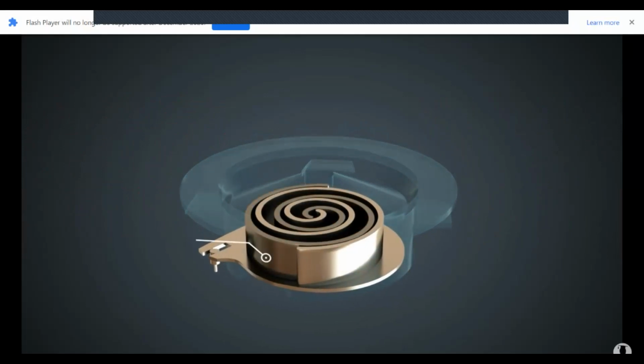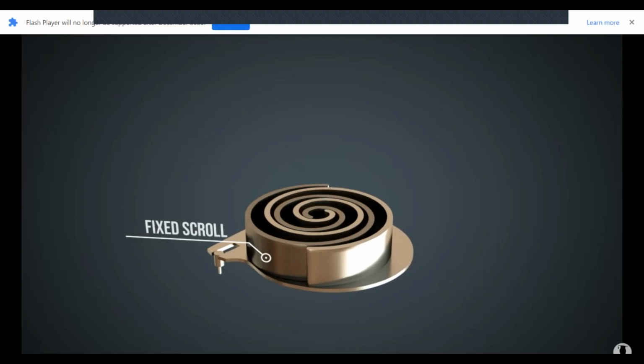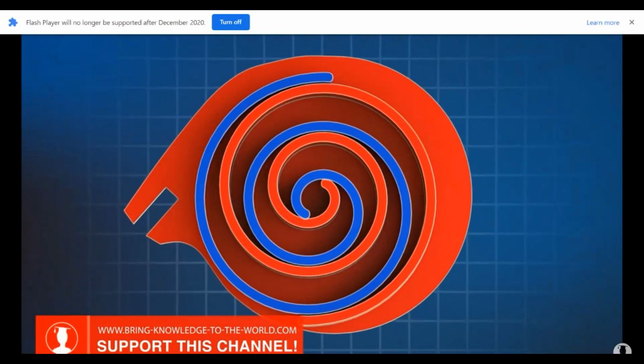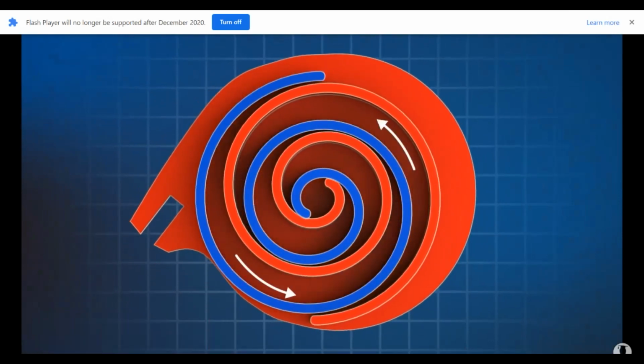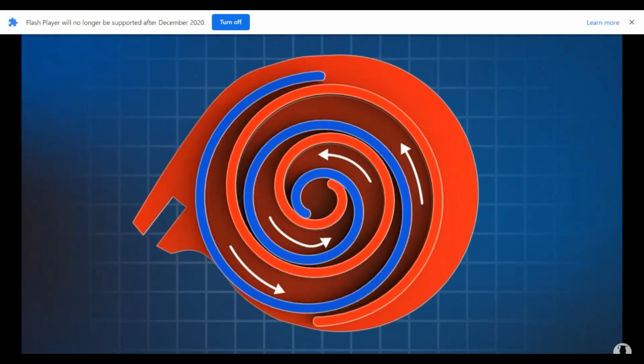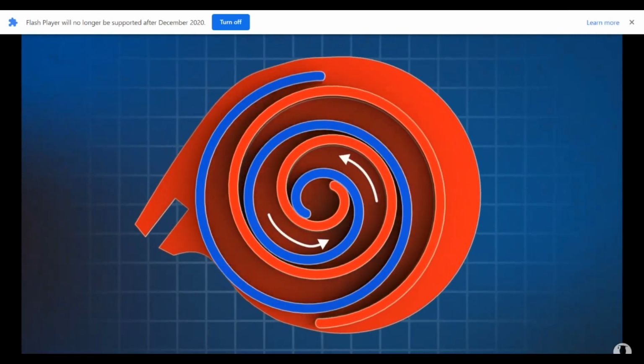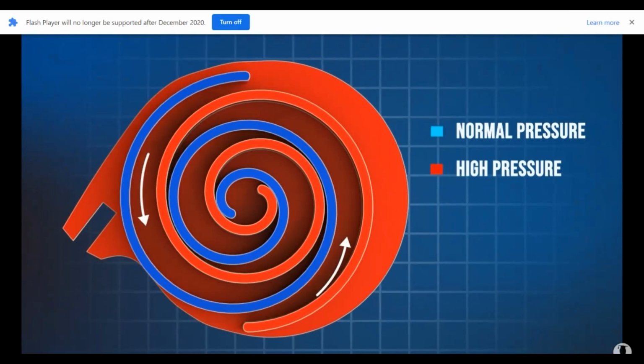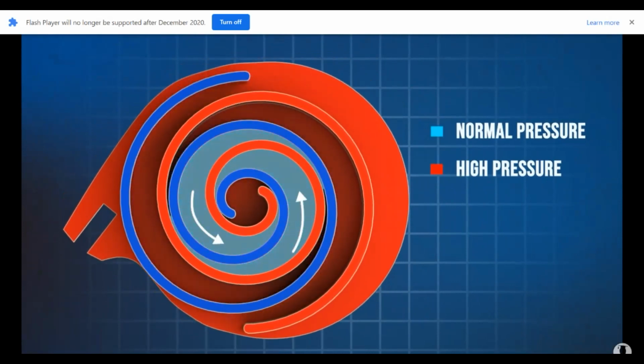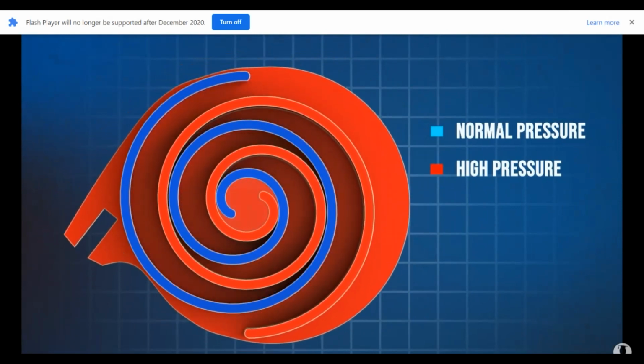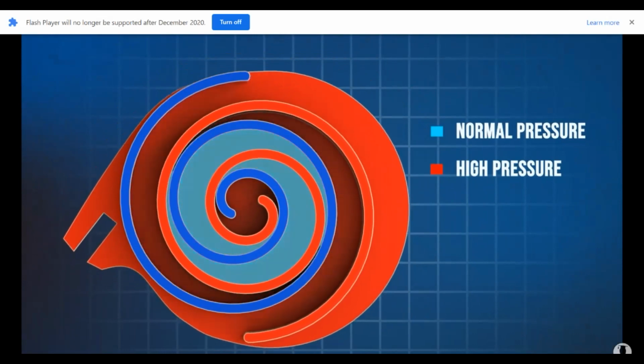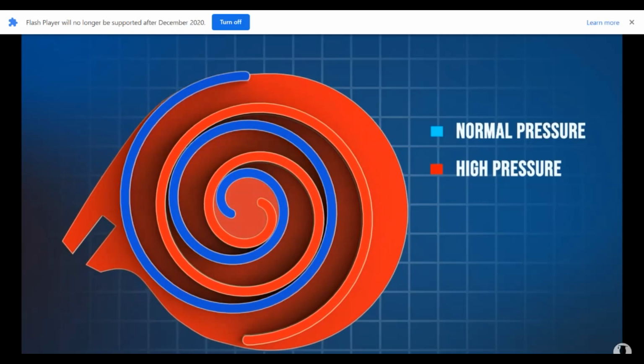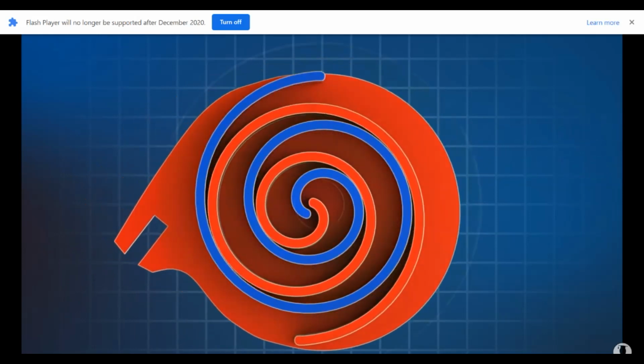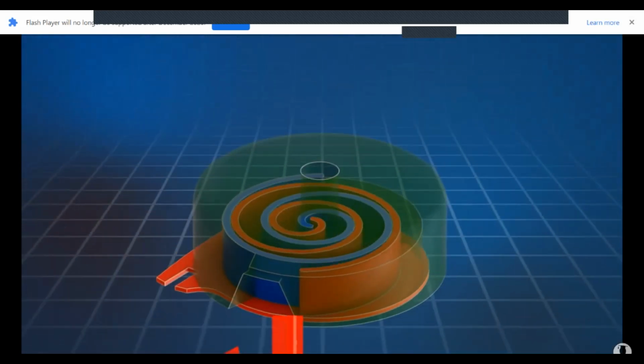For better visibility, only the moving scroll with its base plate and the fixed scroll are now being displayed. The gas is absorbed in the forming chambers, and transported to the center of the scroll set. As the rotation progresses, the chambers become much smaller, so that the gas is compressed within the compressor. Therefore, this type of compression is called internal compression. In the middle of the scroll housing, which is shown here in green, is a discharge port, through which the compressed gas can escape. Normally, there is also a check valve.